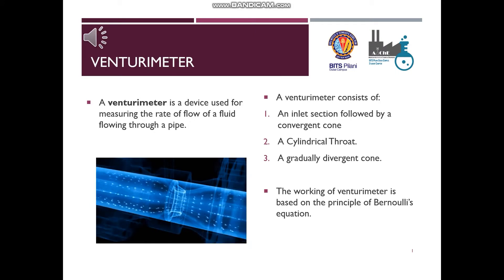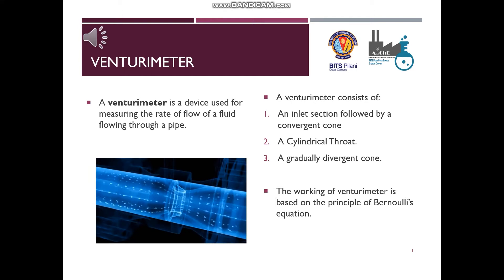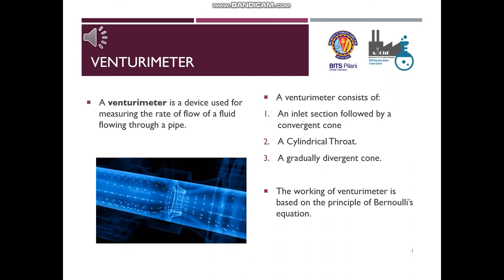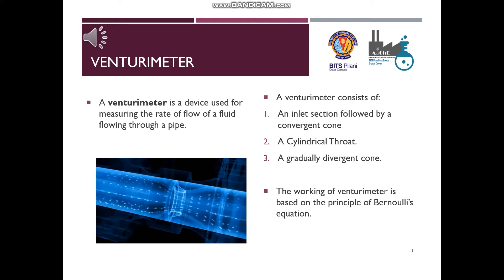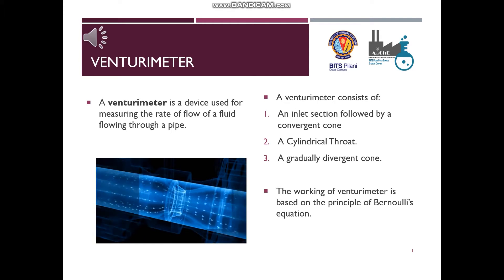The inlet section of the venturimeter is of the same diameter as that of the pipe, which is followed by a convergent cone. The convergent cone is a short pipe which tapers from the original size of the pipe to that of the throat. The throat is a short parallel-sided tube having its cross-sectional area smaller than that of the pipe. The divergent cone is a gradually diverging pipe with its cross-sectional area increasing from that of the throat to the original size of the pipe.